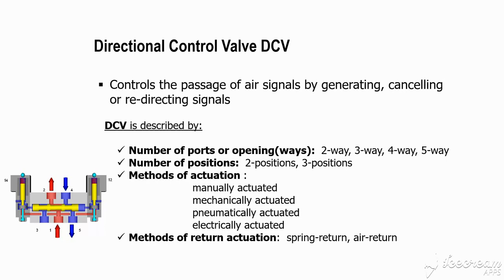Three ports means three holes in the valve. Two positions means a normally closed position and an open position — when you press the valve it goes to open, and when you release it returns to normally closed. Similarly, a 5x2 valve has five ports and two positions. When you operate this valve, one side opens and the other side closes.